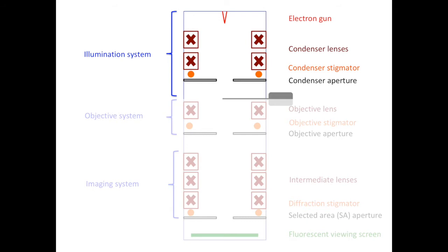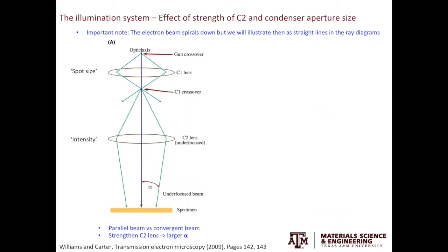We will look at how the beam characteristics will be affected by changing the parameters in those components. We have already discussed the electron sources and the condenser stigmator in the previous videos. Here, we will focus on the C1 lens, C2 lens, and the size of the condenser aperture. The C1 lens controls the spot size, and the C2 lens controls the intensity.